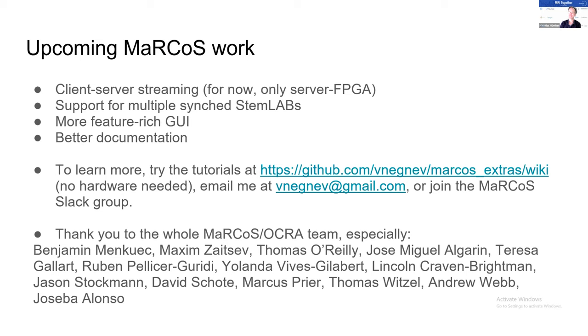Thank you very much, Benjamin and Vlad, for the presentations — it's quite an exciting and powerful project. A question came in about whether the hardware could be used with a 1.5 Tesla system. The answer is not with the current Red Pitaya, which has only a sample rate of 122 MHz. However, it is theoretically possible to port Marcos and Flopra to another hardware platform with a higher sample rate, or to use external analog mixing.